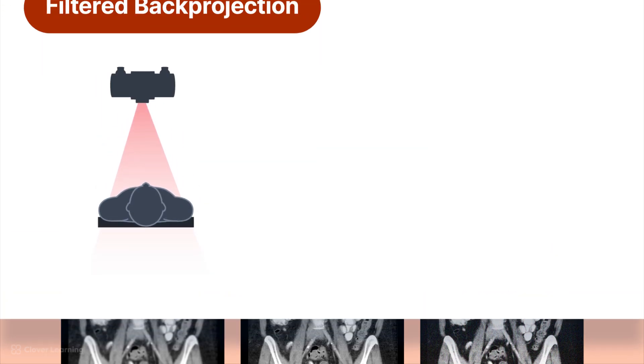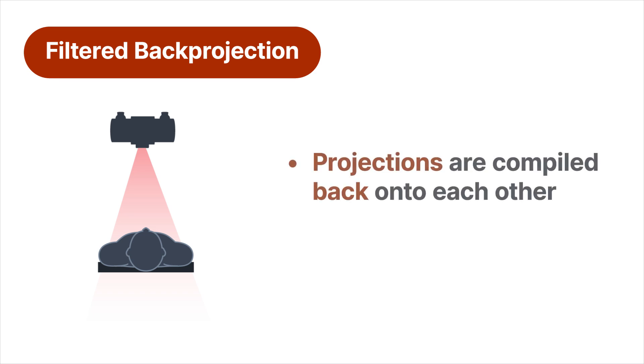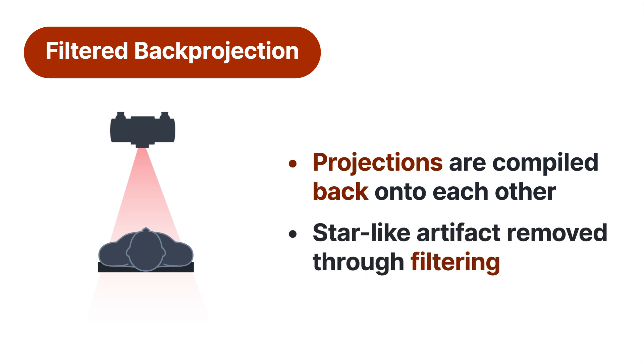The last step in the reconstruction process is something called filtered back projection. Before this convoluted information can be viewed, it has to undergo this process. The name is self-explanatory - this is the process through which projections are compiled back onto each other. And the reason it's called filtered back projection is in CT, we use a special mathematical filtration process that removes a star-like artifact that would otherwise be present through the back projection process. Remember in CT scanning, an individual slice is actually the compilation of multiple projections or views from around the patient. All of these views or projections do have to be compiled back onto each other, and it's through the process of filtered back projection that we make that happen.